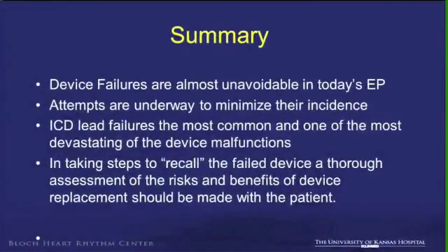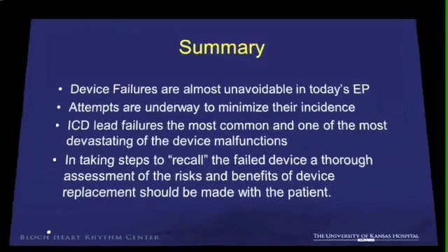So my summary: device failures are almost unavoidable in today's EP due to innovation. We try our best, but attempts are underway to minimize their incidence. The key is bridging the gap between identifying the failure and recalling the leads. ICD lead failures are most common, and one of the most devastating of device malfunctions. In taking steps to recall the failed device, a thorough assessment of the risks and benefits of device replacement should be made with the patient.